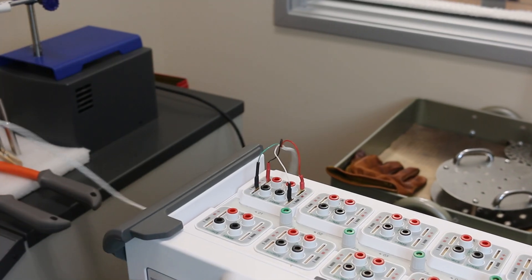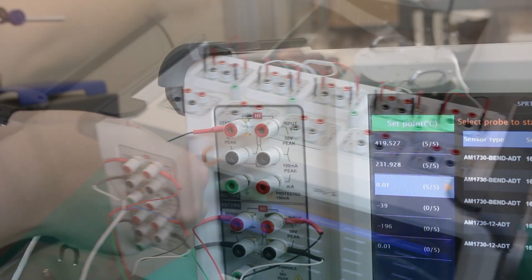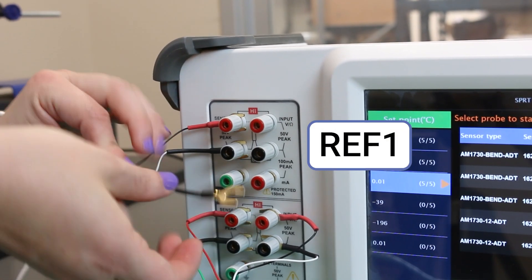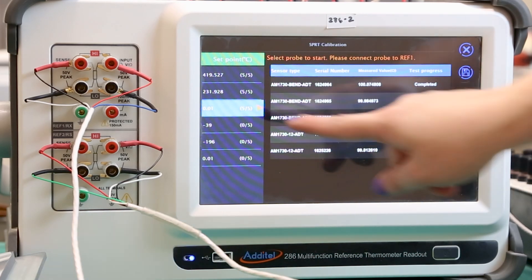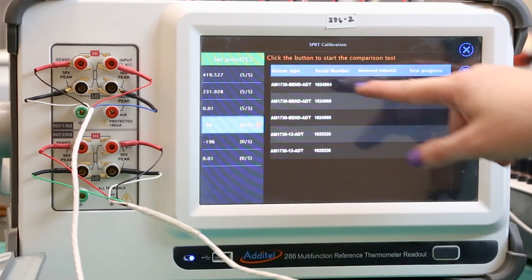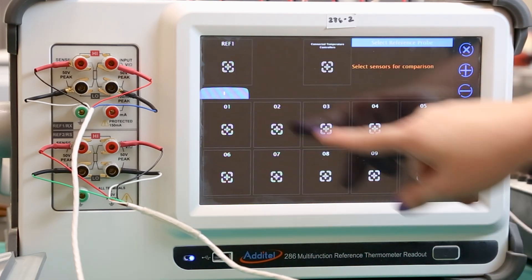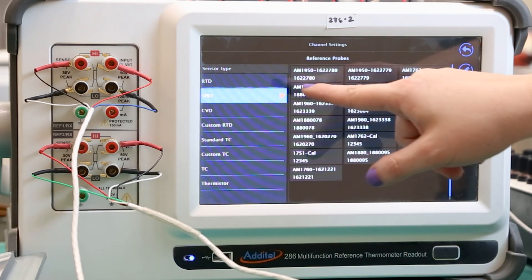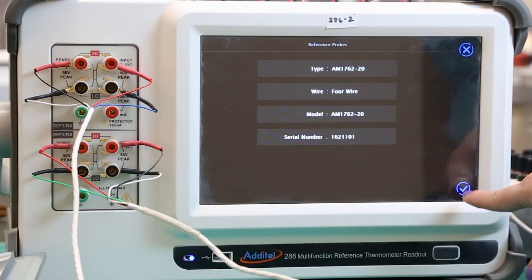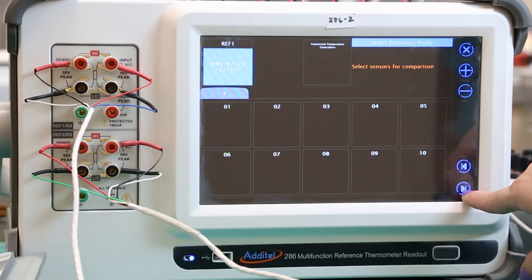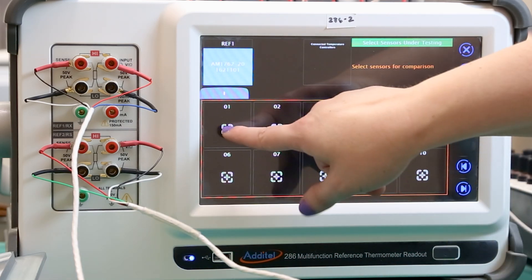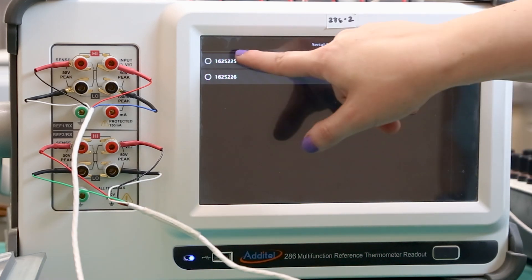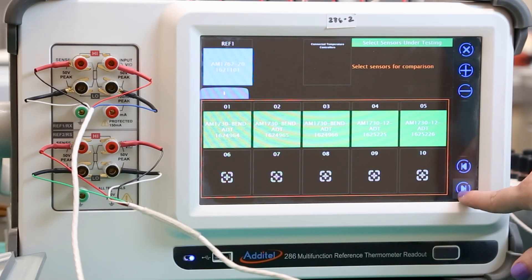Since the negative 39 degree bath is large enough to fit all of the probes at once, we can connect all five of them to the ports on the top of the 286. We will also connect the reference SPRT to the REF1 channel on the front of the 286. Now we can add each of the probes for the automated measurement. Select the first probe section, then add the reference SPRT from a list of preset probes. Then press the next button and add each probe to be measured to the corresponding channels they're connected to.